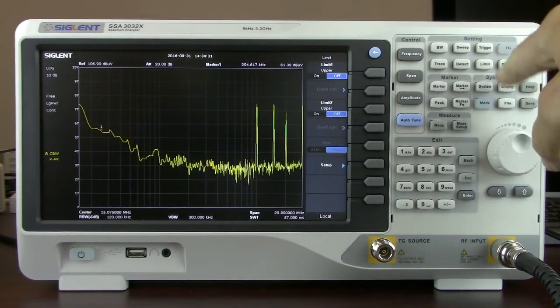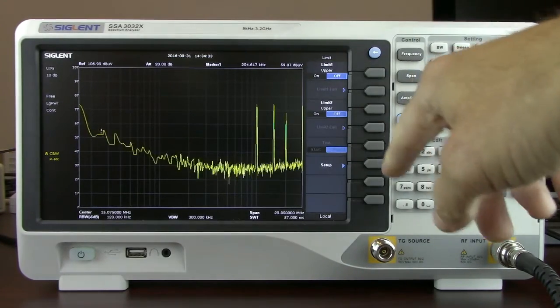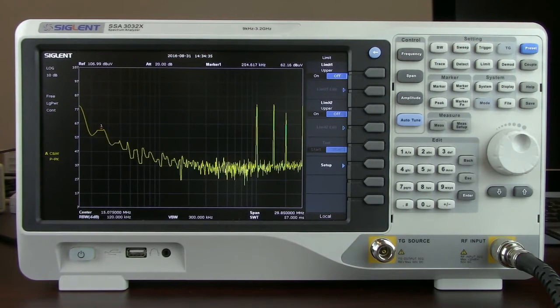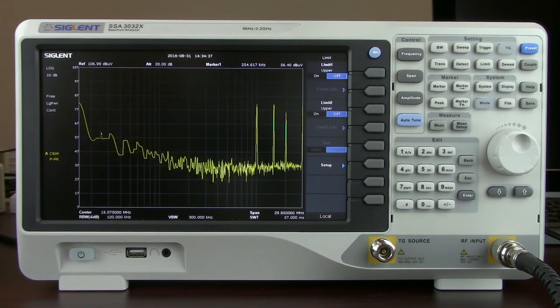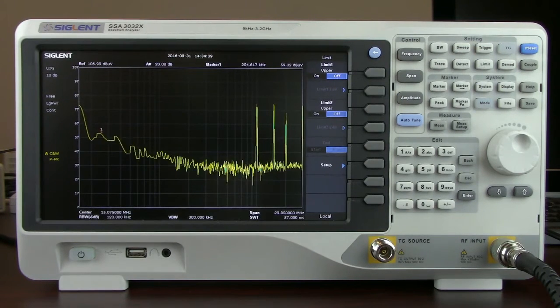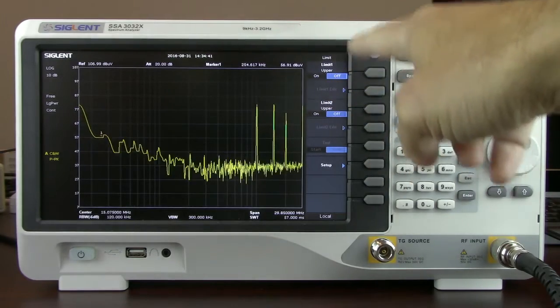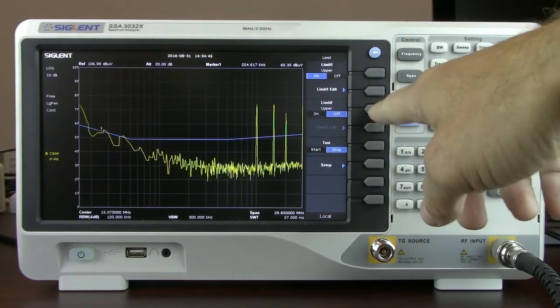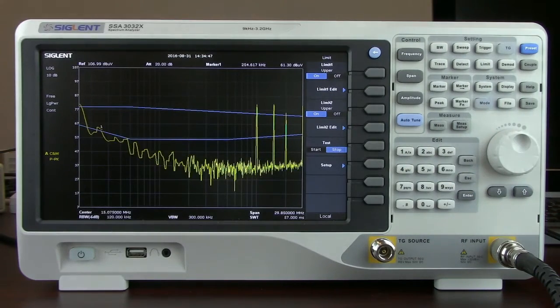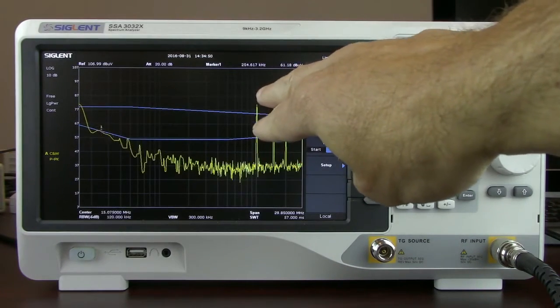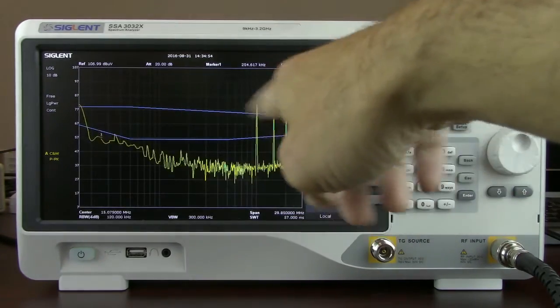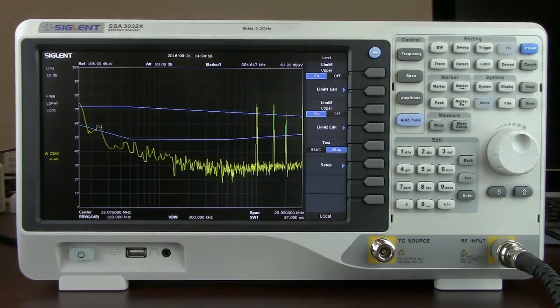Pressing the limit key we've got two limit lines. Many spectrum analyzers will not have two full limit lines. They'll have an upper and a lower. In this case we've got two limit lines that we can select to be upper or lower. We're going to turn on limit line 1 and turn on limit line 2. Now we can visualize the two limit lines we need to meet for this particular application, and our electromagnetic performance of our device under test shown under the yellow trace here.